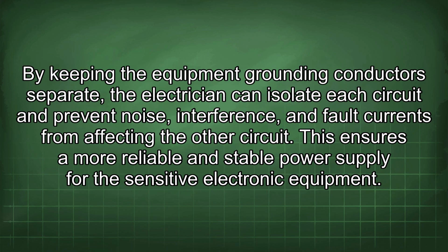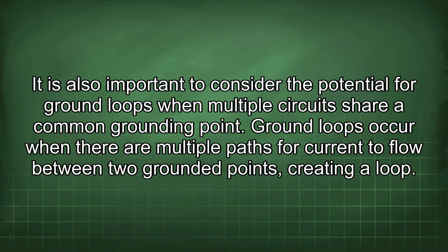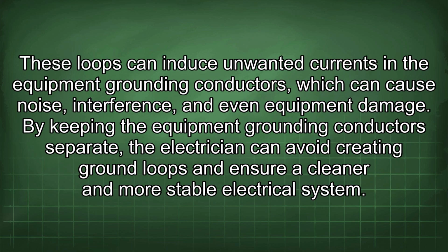By keeping the equipment grounding conductors separate, the electrician can isolate each circuit and prevent noise, interference, and fault currents from affecting the other circuit. This ensures a more reliable and stable power supply for the sensitive electronic equipment. It is also important to consider the potential for ground loops when multiple circuits share a common grounding point. Ground loops occur when there are multiple paths for current to flow between two grounded points, creating a loop. These loops can induce unwanted currents in the equipment grounding conductors, which can cause noise, interference, and even equipment damage. By keeping the equipment grounding conductors separate, the electrician can avoid creating ground loops and ensure a cleaner and more stable electrical system.